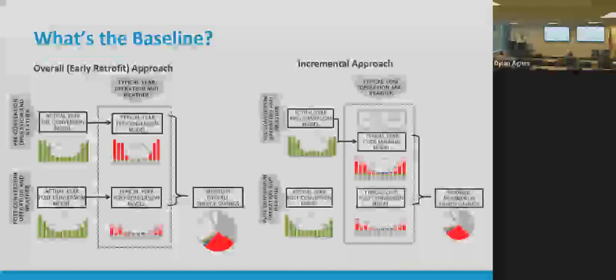Same process - start with actual data versus actual weather data. Then we take that and use all the same inputs, but just improve the efficiency of the equipment to meet code minimum. So maybe the boiler wasn't code minimum anymore, or the compressor wasn't, or the air conditioner wasn't code minimum. Then you just upgrade all the equipment, but you still have a calibrated model. So this is what we call incremental energy savings - you're still able to use actual collected field data to build a calibrated model and then apply it to new equipment, but you still have all the same loads and schedules.